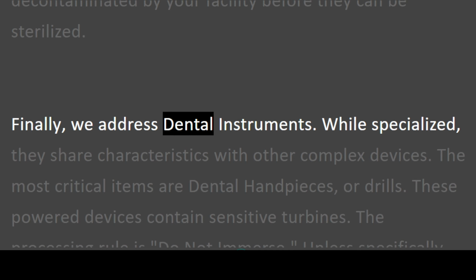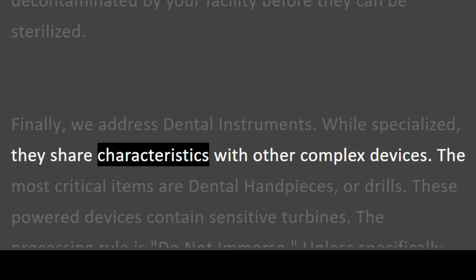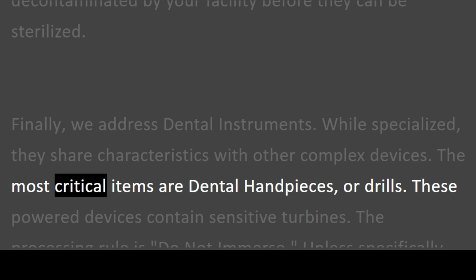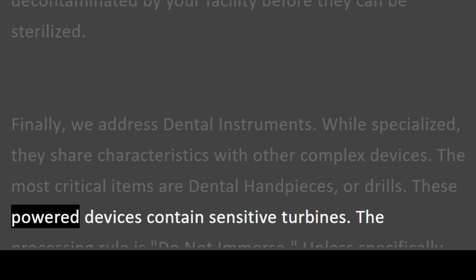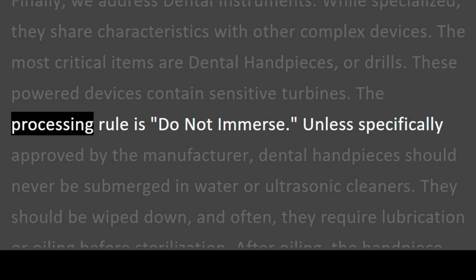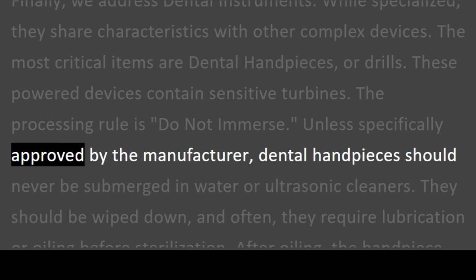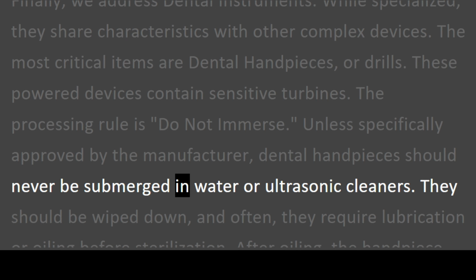Finally, we address dental instruments. While specialized, they share characteristics with other complex devices. The most critical items are dental handpieces, or drills. These powered devices contain sensitive turbines. The processing rule is do not immerse. Unless specifically approved by the manufacturer, dental handpieces should never be submerged in water or ultrasonic cleaners.